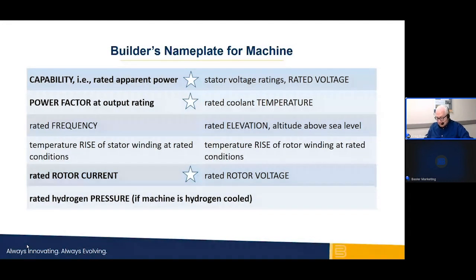The owner who is in possession of the machine's capability curves and commissioning report has a treasure that pays handsome dividends when controls are being retrofit. The capability curve of the synchronous machine tells the story of critical importance to controlling and protecting the machine from unsafe operation. Next slide, please.